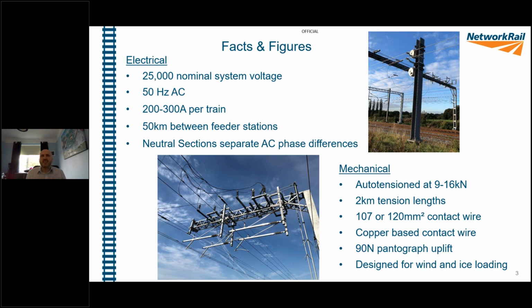Nominally, there's about 50 kilometres between our feeder stations, and the feeder stations are the point at which we bring an external supply in from either National Grid or the distribution network operator onto the railway. We have other sites in between those feeder stations that are there for the purpose of voltage regulation, paralleling sections together, and also operational reasons and switching.